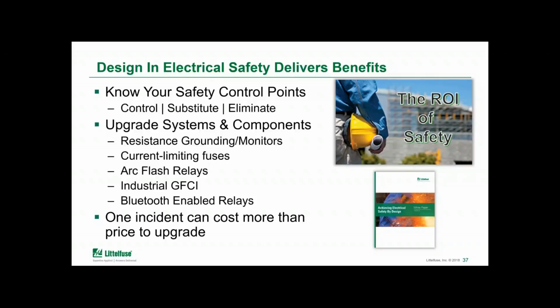Now, by upgrading components and systems in the facility, perhaps looking at resistance grounding, looking at replacing older fuses with current limiting fuses, looking at arc flash protection relays, considering industrial GFCIs or Bluetooth-enabled relays, those all allow you to design in safety. And in many cases, they're not any more expensive than some of the typical devices you would use anyway. And even with a small differential, that return on safety is certainly worth it.